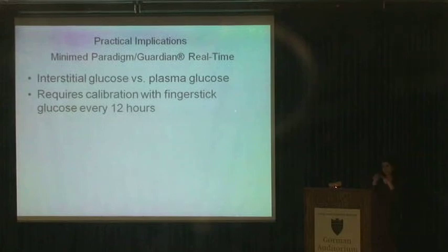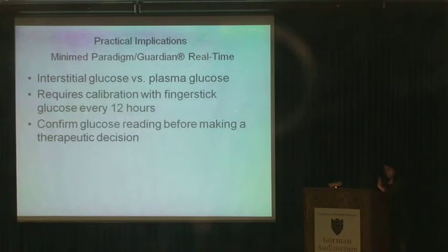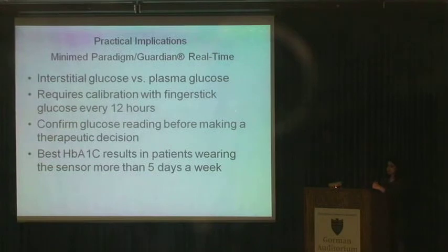You have to calibrate it with your finger stick. Most of the devices need calibration twice daily, so it doesn't replace the finger stick checks. Again, FDA has told us that you have to confirm the reading that the sensor gives you with a finger stick before you make a decision.